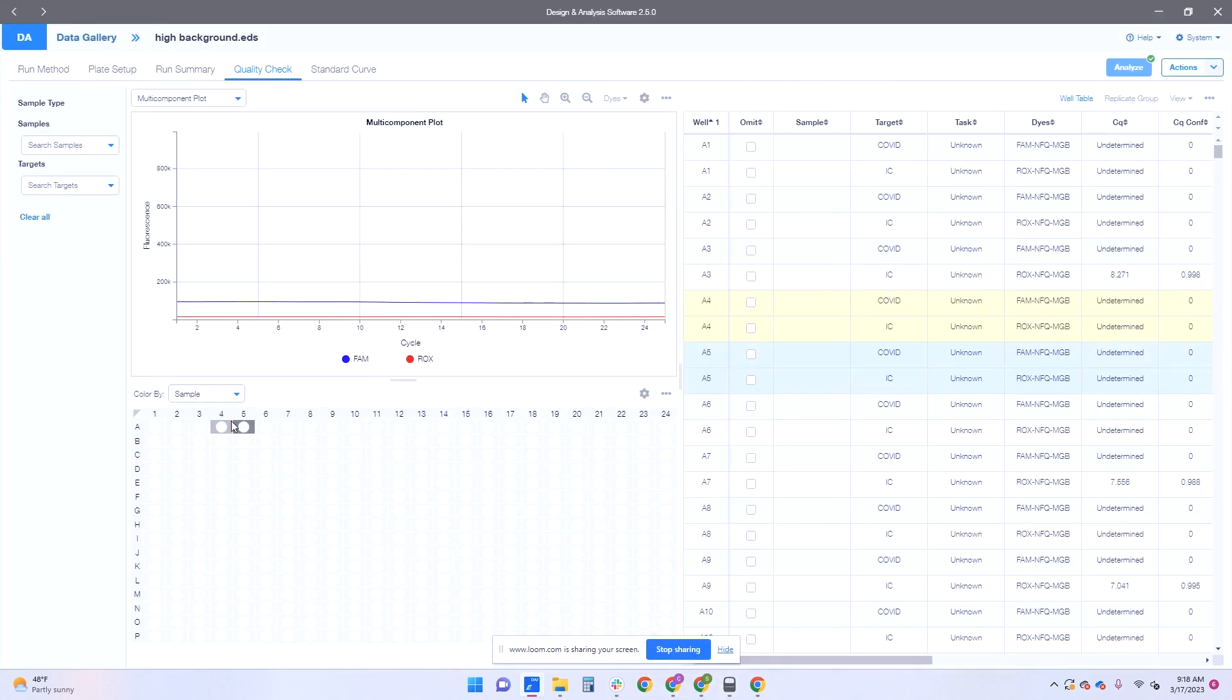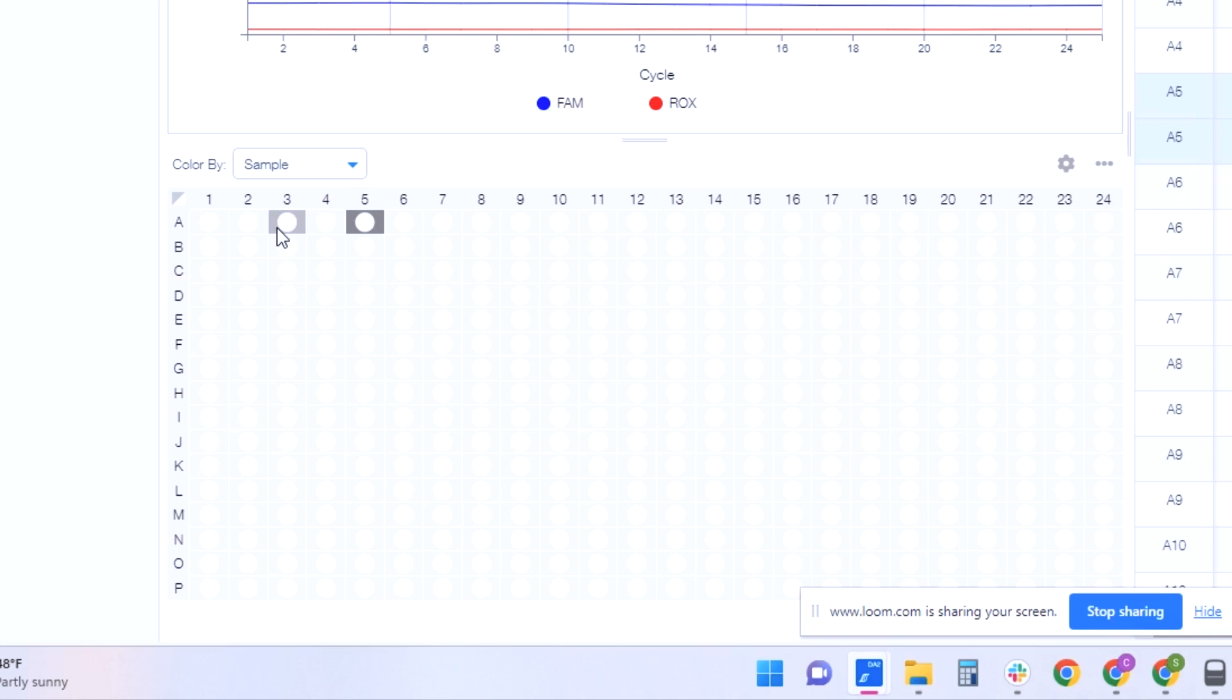Now if you're not doing that calibration plate and you just wanted to check from a day-to-day standpoint, you can run that water plate and you can look to see if there's high fluorescence. So here let me show you an example. So if you're just running samples every day and you have an empty well, you can just check to see if that has high fluorescence per well.